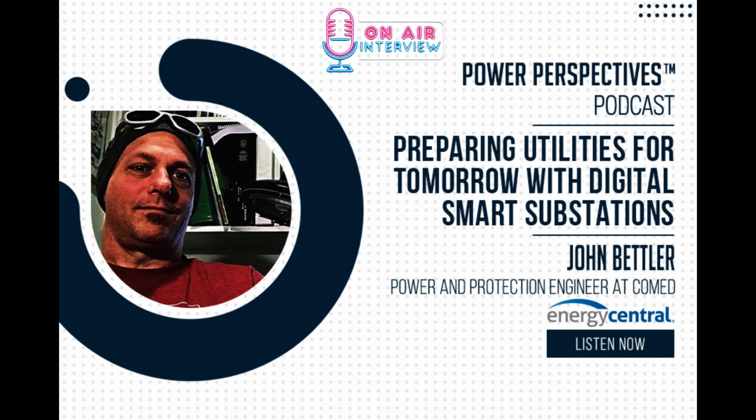On our 34 kV, because we're about to do our fourth and fifth 34 kV substation, we have that down, as long as the topology doesn't change to any great effect. By topology, I mean our planning department creates a one-line diagram, which has a certain number of feeders on a bus and where transformers get connected. Our designs are done. Now it's going to come down to incorporating the template settings, doing name changes, being out there to support the field, and training engineers and technicians in new areas on how it works. But as far as that goes, it's been super easy once we got through the growing pains.